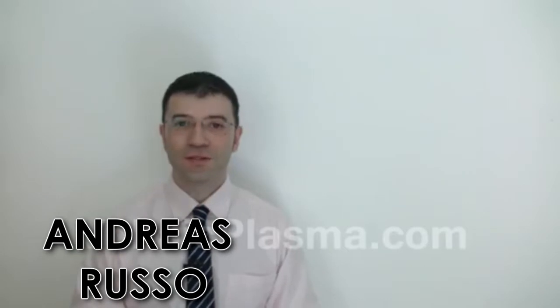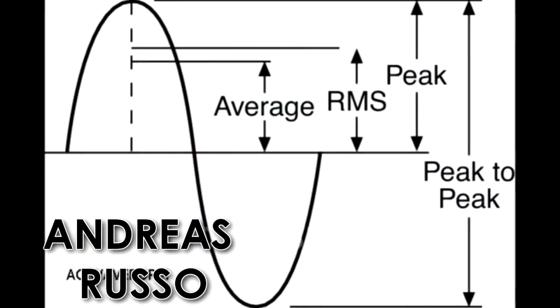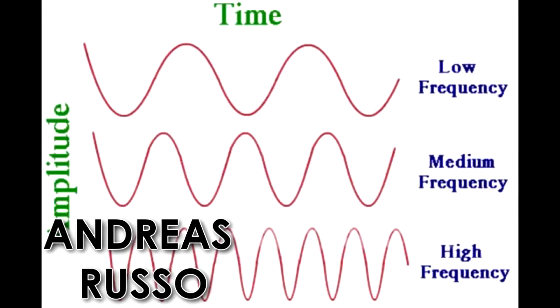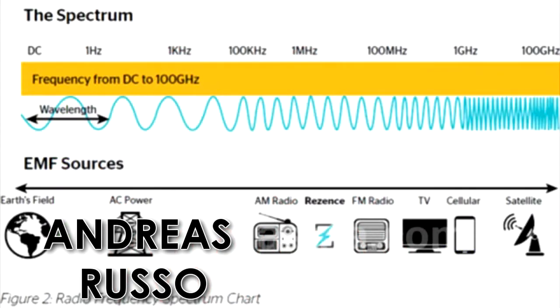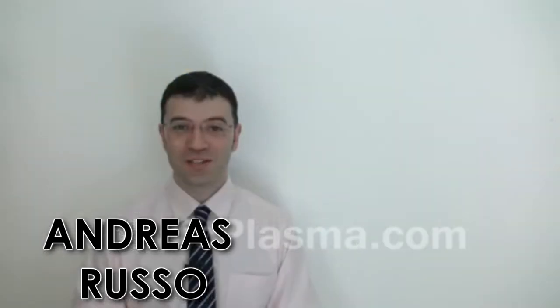If we were to use the same peak-to-peak voltage of 50 Hz as found in domestic supply, we would experience an electric shock. The magic is in the operational frequency of these devices. The frequency output generated by these devices starts from 50 kHz. Note that this is 50,000 Hz and not 50 Hz. This higher frequency avoids the undesired electromuscular stimulation, which in turn avoids electric shocks.